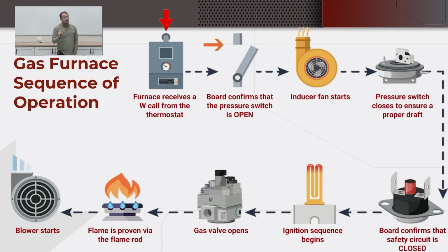You'll still see some thermostats that let you select whether it's a furnace or electric heat. That's one of the big distinctions: do you call for the blower right away? You don't get a G call traditionally when you have a call for heat in a gas furnace, because you want everything to heat up and create a draft before the blower comes on and cools everything down again. You don't want a cold draft in the house, and you also want the flue to heat up in traditional furnaces so it drafts better, and when the air first blows out, it blows out warm right away. That's why the blower doesn't come on right away. Does that make sense? On a heat pump, G calls the blower, and W is your heat if it's electric heat, or Y, and then you have the O, obviously.